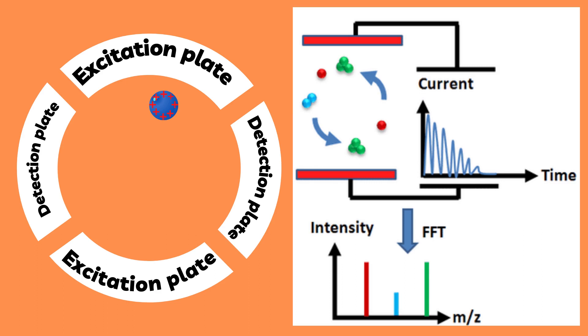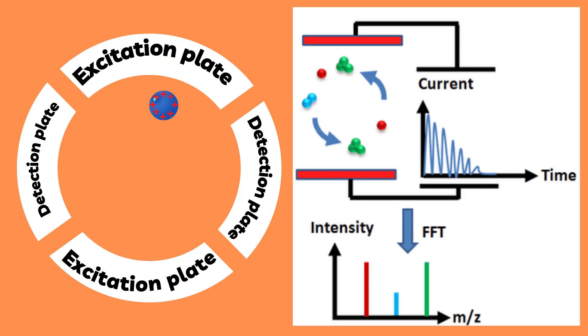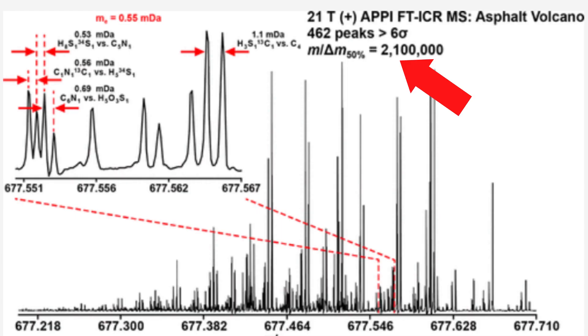The reason why FT-ICR achieves such high resolution is that every revolution — in other words, each time the ion completes a spin in the device — we get another point of measurement. This results in an incredibly high resolution, in fact even above two million, which is just beyond anything we've seen on any of these other mass spectrometry devices.